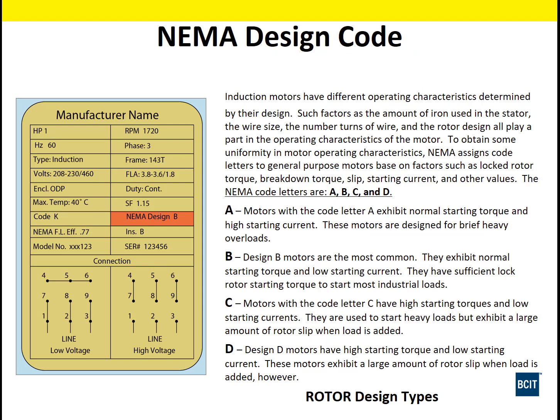Okay, NEMA design codes. Down here at the bottom, rotor design types. Okay, that's on the nameplate too. We have our rotor design type. So if we want to have specific torque characteristics, we know what type of motor design code we're going to have. If it's for a squirrel cage motor, we want it to have a very good starting torque, but we don't care too much about the speed regulation. Okay, we might want to have a D. It's going to have a higher slip at full speed, but it'll have a really high torque at startup. So we can specify those with this.